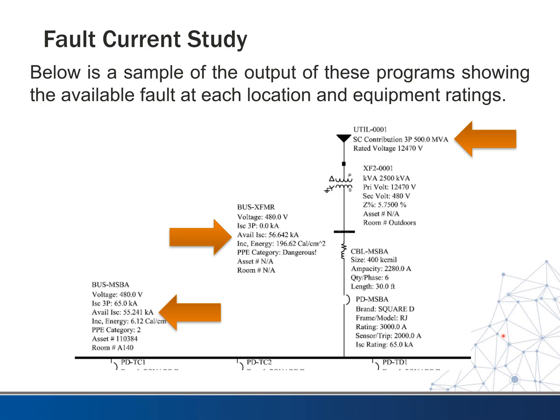Going back to our snapshot of the model, we can see where we've already marked the available fault current. For each bus, the ISC 3P shows what the equipment is rated for — for example, this breaker has an ISC rating of 65. We want to make sure that the equipment's rating is larger than the available fault current. If it's lower, then we have a problem and we have to make some recommendations to fix that.